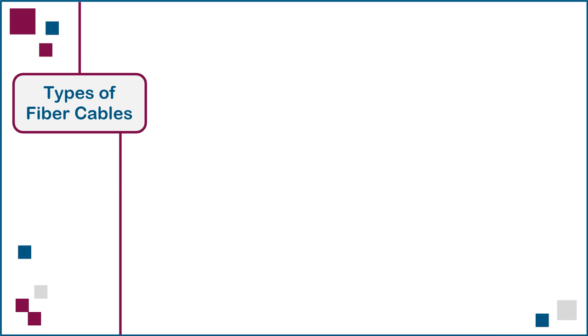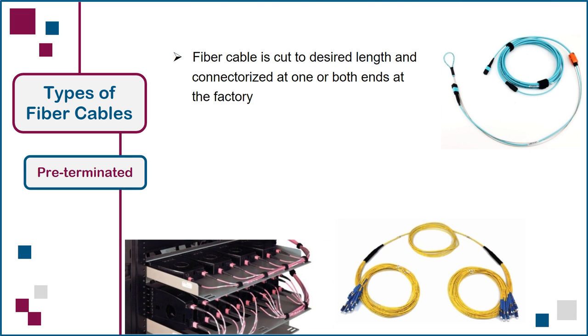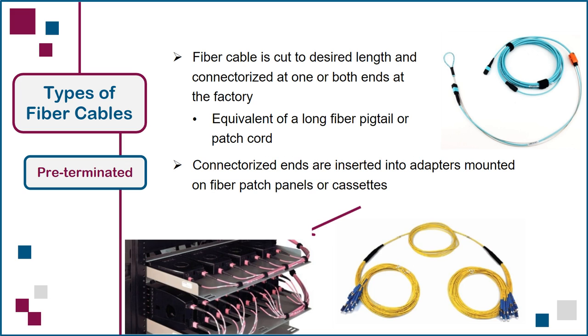The fourth type of cable construction is pre-terminated, where the fiber cable is cut to the desired length and connectorized at one or both ends at the factory by the manufacturer, essentially the equivalent of a long fiber pigtail or patch cord. After the cable is installed, the connectorized ends are inserted into adapters mounted on fiber patch panels or cassettes at one or both ends, which eliminates all connectorization time and minimizes termination errors. Note that pre-terminated or pre-term cabling was initially developed as a solution for data center computer rooms, but it can also be used in commercial building distributor rooms or any other environment where the required cable lengths can be accurately measured.